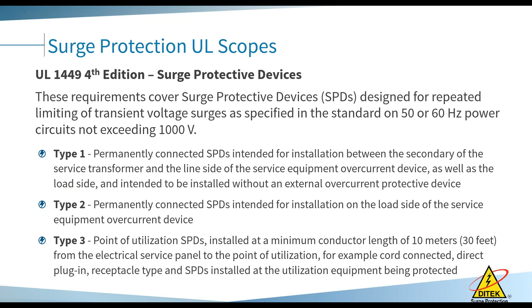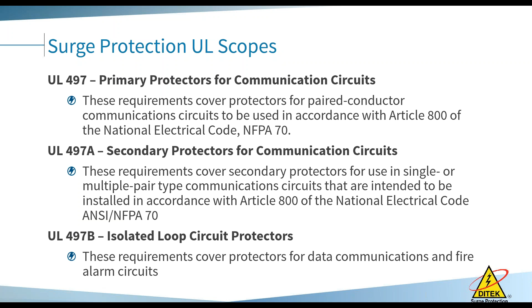On the low voltage stuff, these are primary like communication circuits. UL 497 is just primary protection for building entrance by NFPA 70. 497A is communications lines. That's more or less the old POTS lines. And then 497B is anything else low voltage. Our speaker circuits, our PoE, our intercom circuits, SLC, NAC, those all have a 497B listing as well.